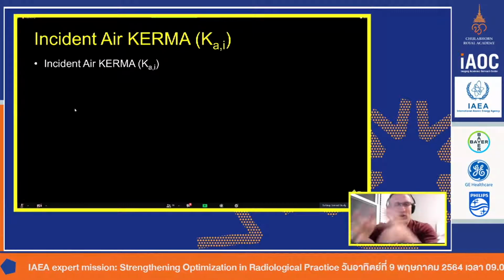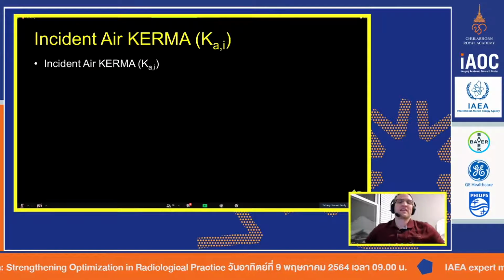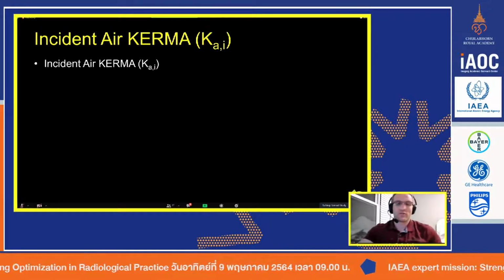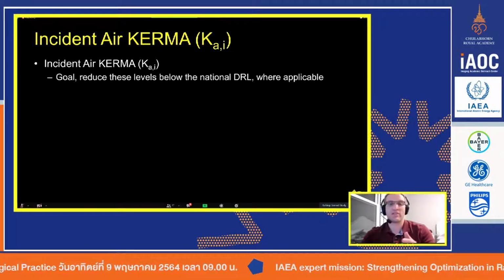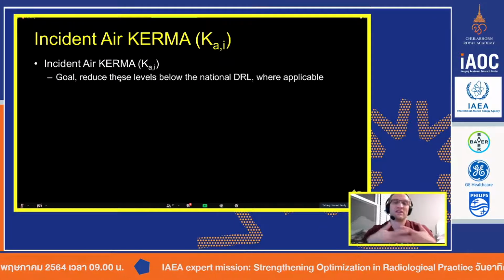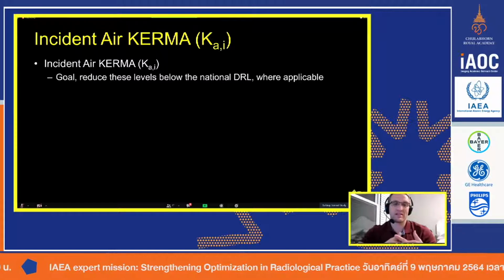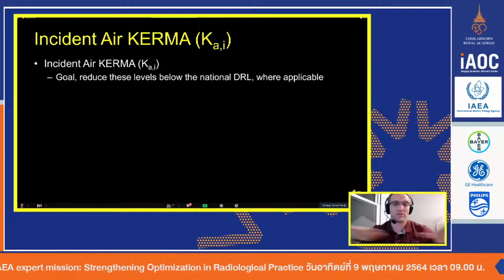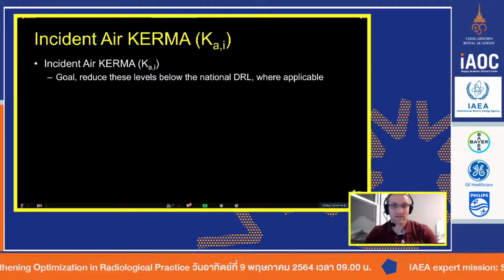But moving on now to incident air kerma. This is the idea of setting up a value now that we can use for a diagnostic reference level. This is what you guys used in Thailand. You used actually not the incident air kerma, you did the entrance surface air kerma. Incident air kerma, remember, does not include backscatter. The entrance surface air kerma does include backscatter.